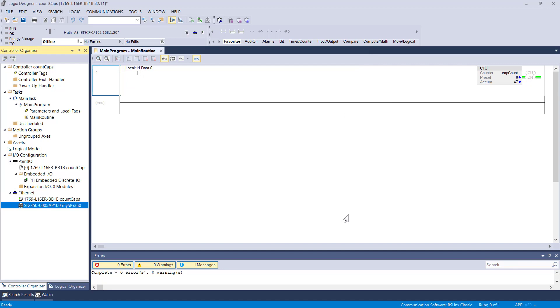The SIG350 comes from the factory set with Boot P active. So you can use a Boot P tool to discover and set the IP address per the MAC address of the device. Or, which is my case, the IP address has already been set to 192.168.1, and then the fourth octet is manually set using the pots there on the front. So if you know the subnet you can dial in the IP address.